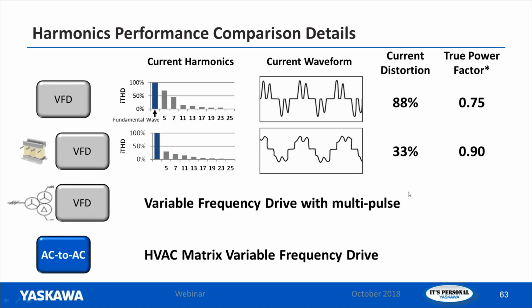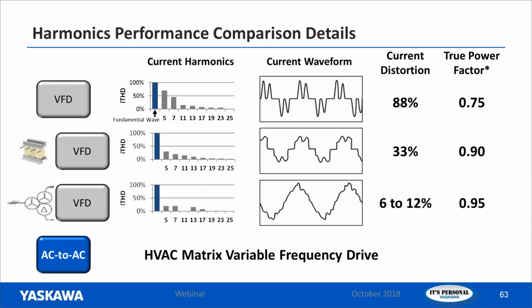Now let's look at another popular option. That would be adding multi-pulse, 12 or 18 pulse, to the circuit. With 18 or 12 pulse, we can get the current distortion down to 6 to 12%. That's another sizable cut in our distortion, and we can get our power factor up a little bit higher. Now we've got it up to 0.95. It's come a long way, this waveform, from the one up top, so that is pretty good. But I did mention earlier I wanted to show the Z1000U HVAC matrix drive as the best option. So let's take a look at that.